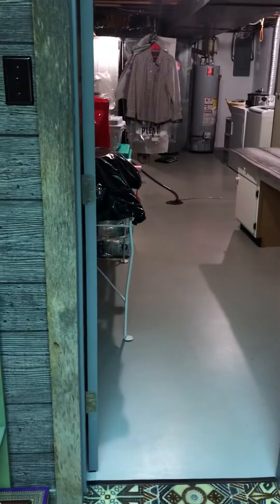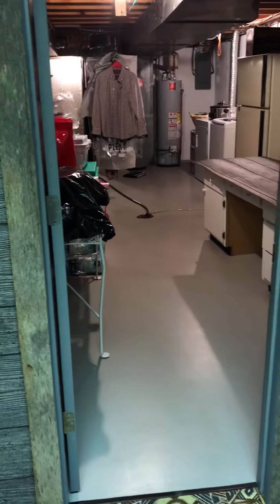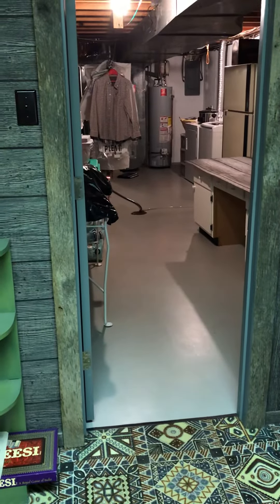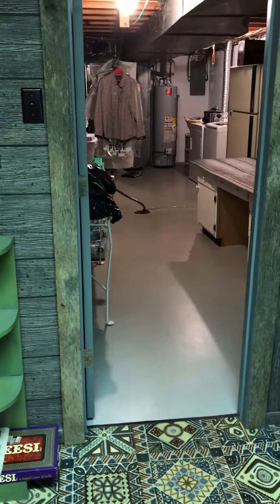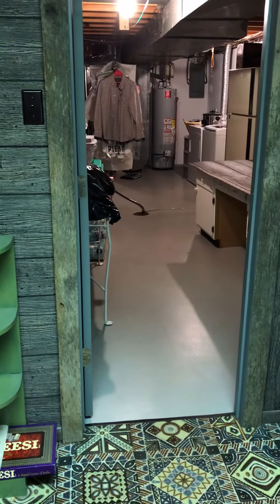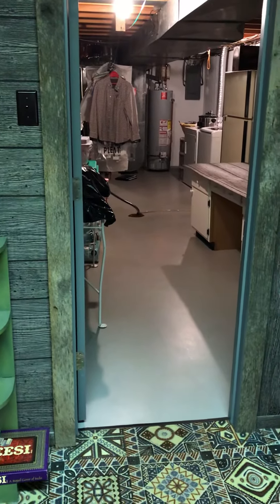Here at Paul and Lynn's house looking at a furnace and possible air conditioner replacement. We're in the basement — not a walkout — in a utility room where the equipment is located. The door width is 26 inches, so we may need to take the old furnace apart to get it out through the door. I'm going to get a measurement on that in a few minutes.